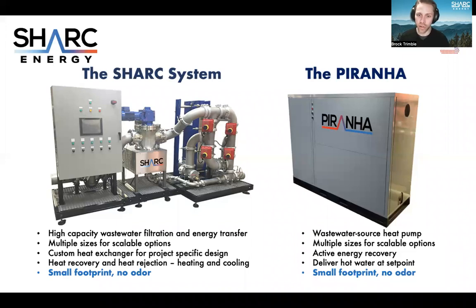So the first that you're going to see here is the SHARC system. This is a wastewater filtration device that allows access to the energy contained within wastewater by temporarily filtering the solids content and discarding it to the sewer, and using that really energy-rich wastewater stream to move into your building space using a paired plate and frame heat exchanger, allowing that energy transfer to or from your system. So with this, we're able to allow the wastewater source to become a heat source or a heat sink, heating or cooling your building space. And that heat exchanger can be customized for your project based on flow rates, delta T's, approach values, et cetera.